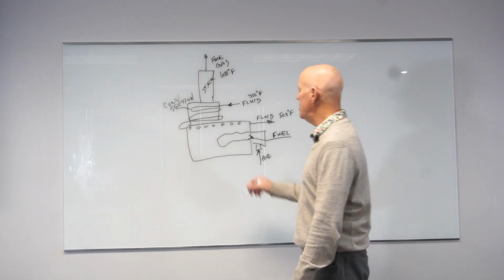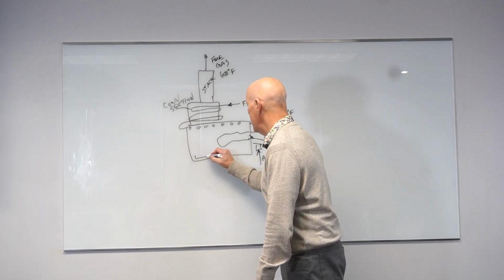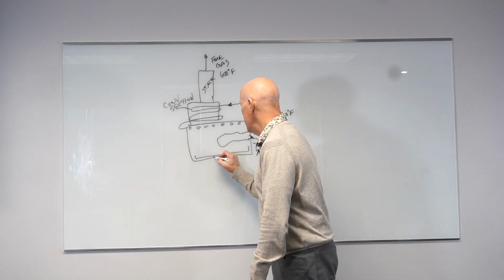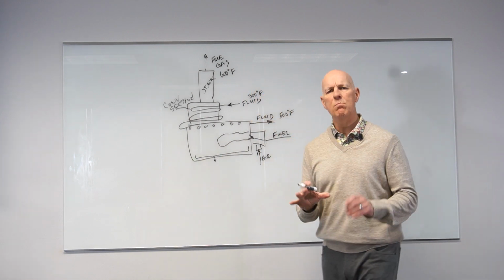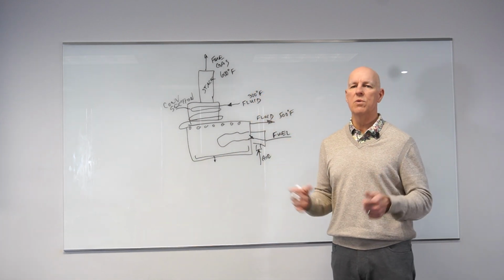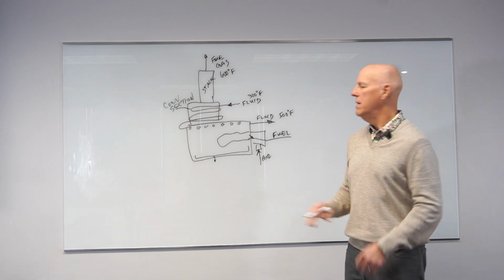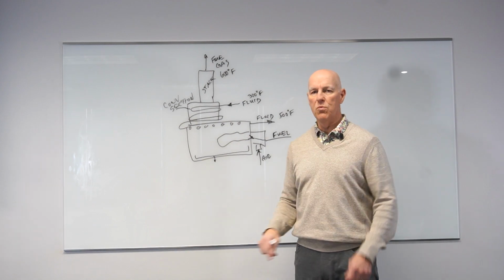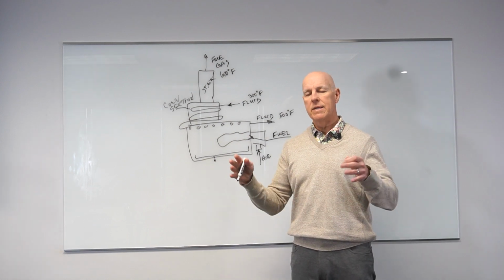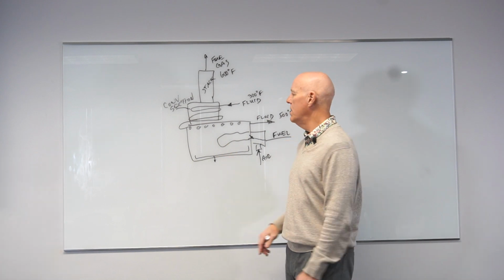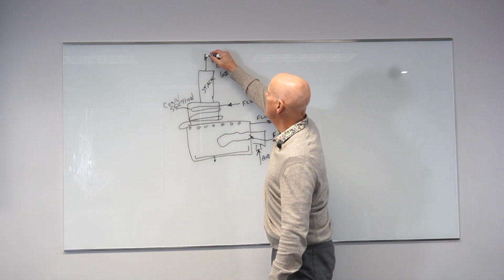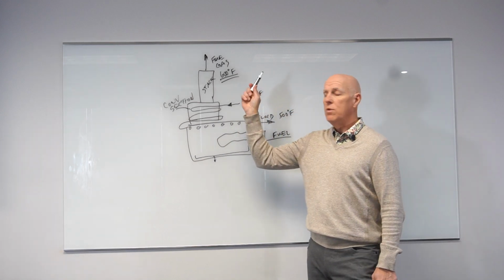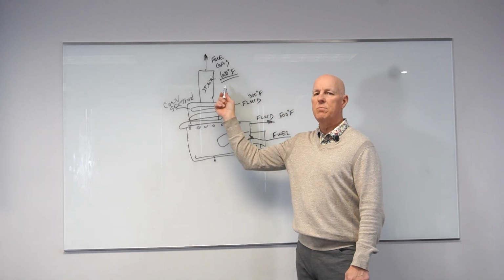Another place that I lose energy is inside this heater. Of course, we have what's called refractory, which is like insulation, and so I lose a little bit through that. Almost inconsequential, like maybe 1% of the duty, 1% of the energy that's used in this fuel firing comes through the wall, because I'm going to insulate that, kind of like a Yeti in reverse. So really what it gets down to is, how do we get this temperature lower? Because we know if we want to increase the efficiency, this needs to be lower.